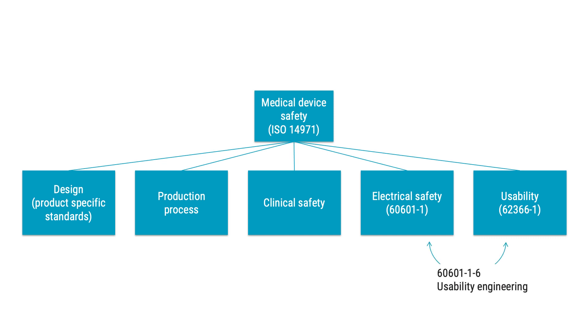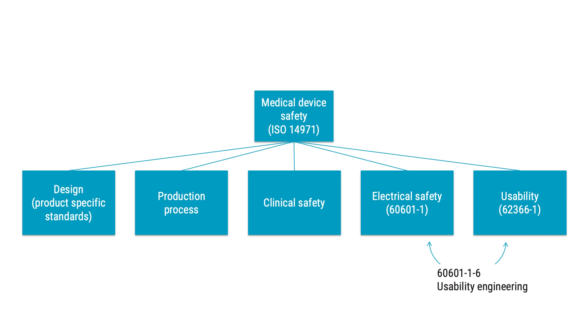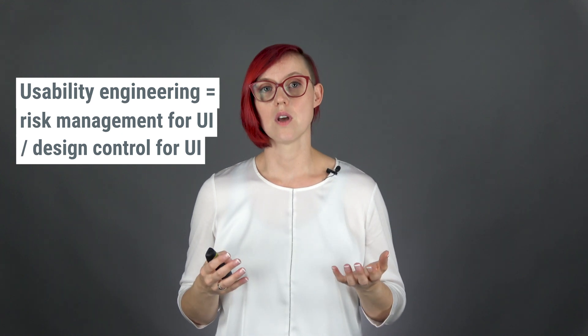As a side note, there is also a standard on usability in the 60601-1 series of standards — that is the 60601-1-6. This standard is similar to the first edition of the 62366-1 standard. Remember, this course is on the second edition and the amendment from 2020, so please try not to get confused. Having said that, you could see usability engineering as risk management focusing on the user interface, or design control focusing on the user interface.